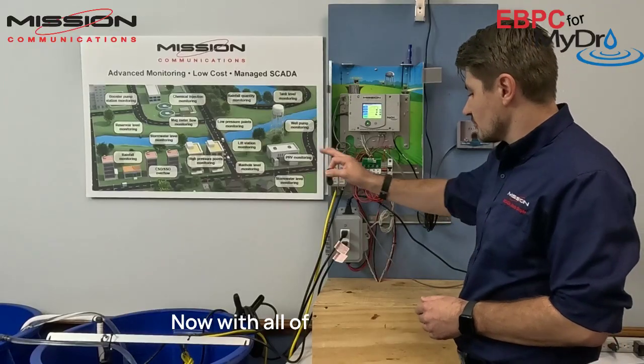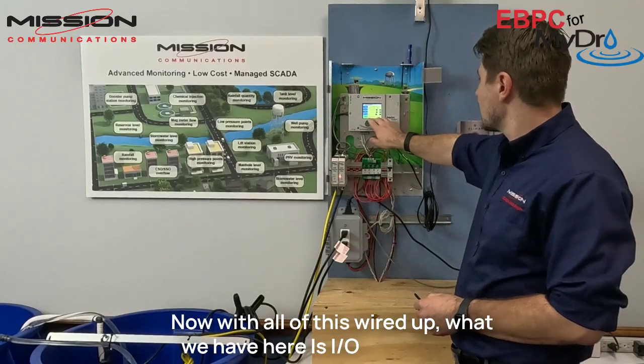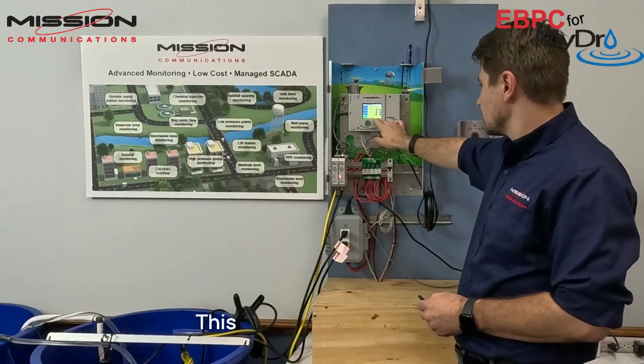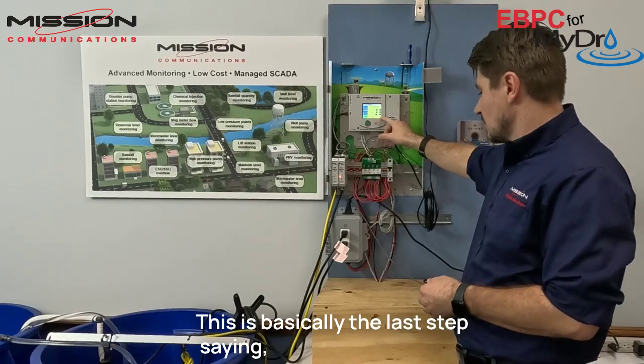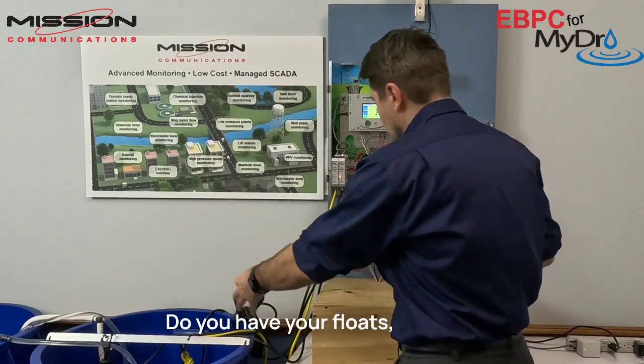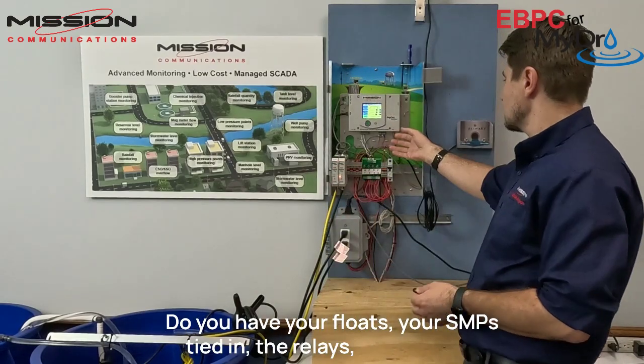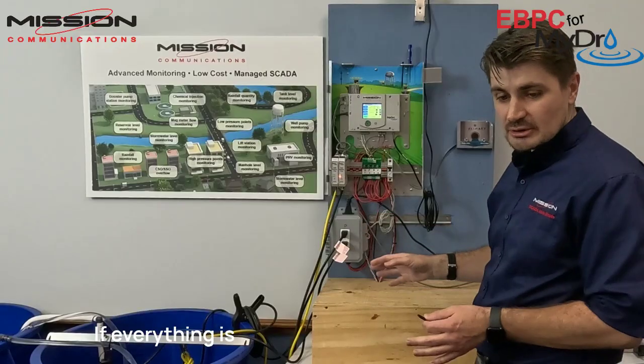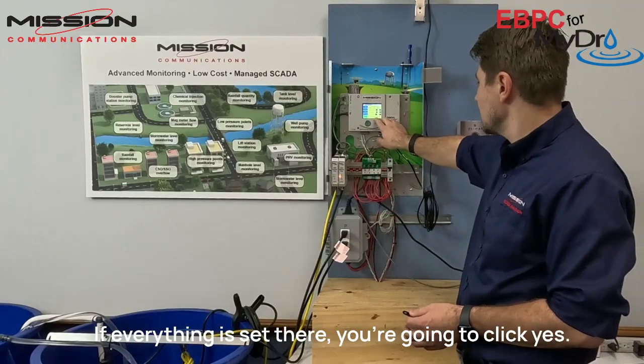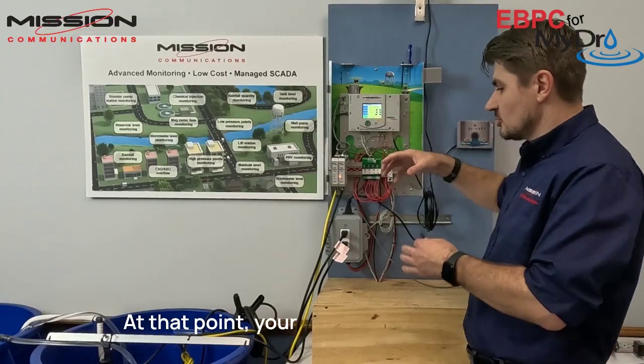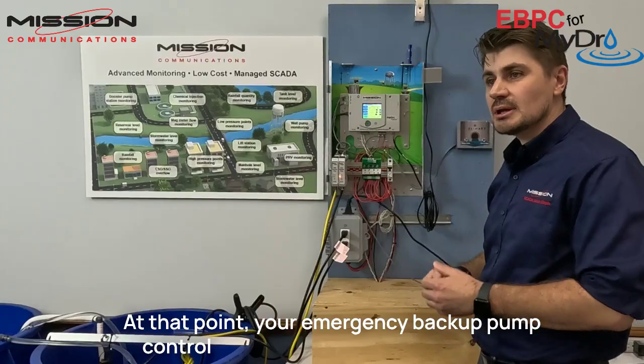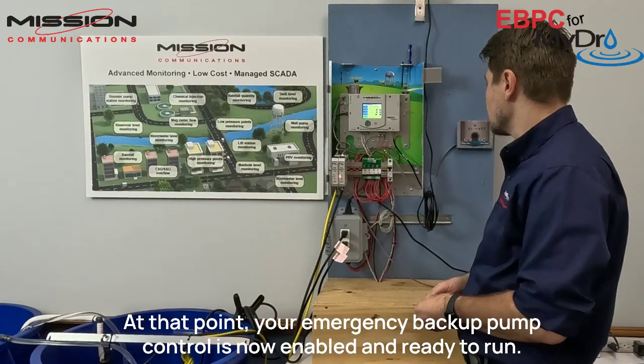Now with all of this wired up, what we have here is IO configured. This is basically the last step saying, is everything wired? Do you have your floats, your SMPs tied in, the relays, the digitals? If everything is set there, you're going to click yes. And at that point, your emergency backup pump control is now enabled and ready to run.